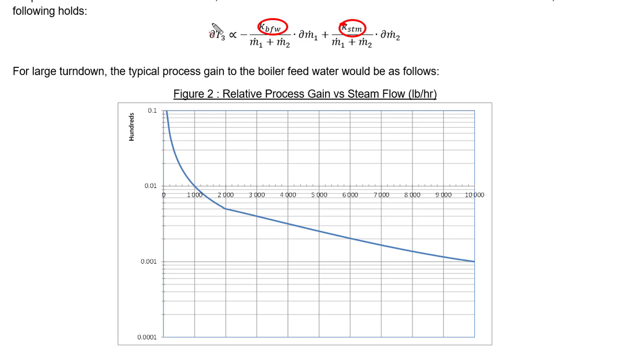Remember, this is the control variable, this is the disturbance variable or feed forward—we're not really measuring or using it—and this is our manipulated variable because we're manipulating boiler feed water. You can see that this is a horrible thing. What are you going to tune it for? Do you tune it for startup conditions with very low gain in your PID algorithm? Or do you tune it for normal operation? And then how do you handle the transition? It gets a bit messy. One has to start questioning the design to see if there's a better way to do this, because this is a blending problem.